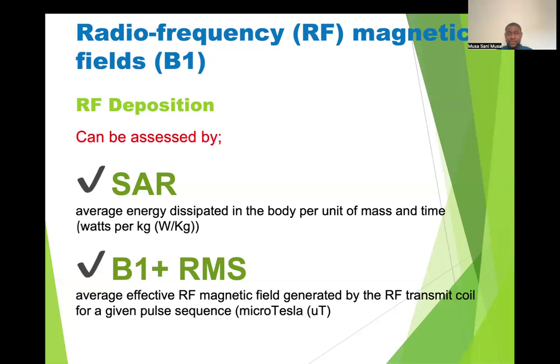Also, it has its own maximum level. This has nothing to do with the weight, whereas this is with the scanner or the particular sequence that you're trying to run. So also it's really important, if your MRI safety experts have given you the conditions of implants. So do you know how to check these settings on your MRI scanner? Do you know how to monitor the patient to make sure you've scanned the patient within this acceptable level?